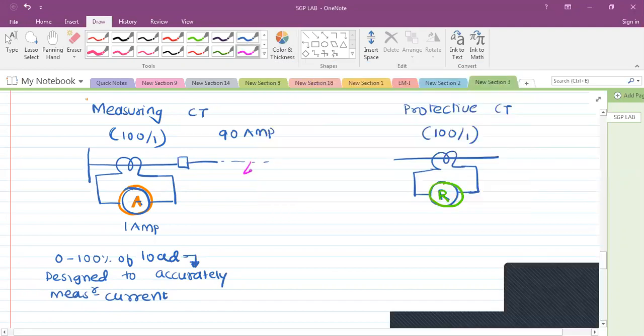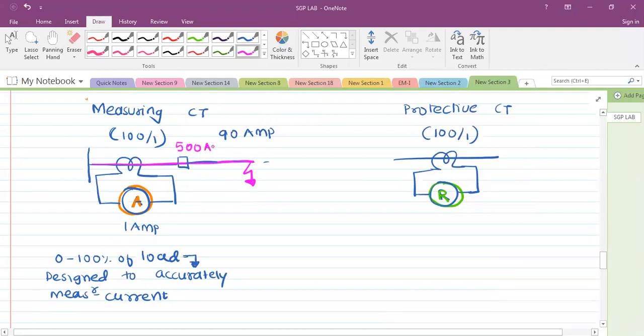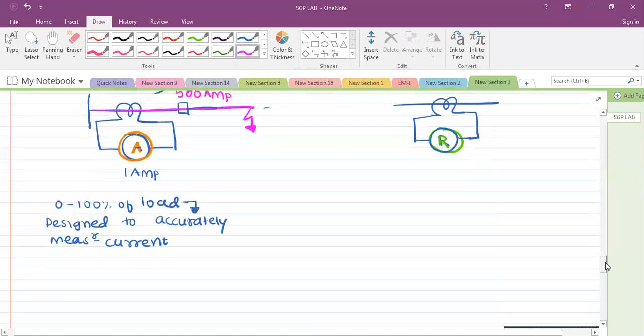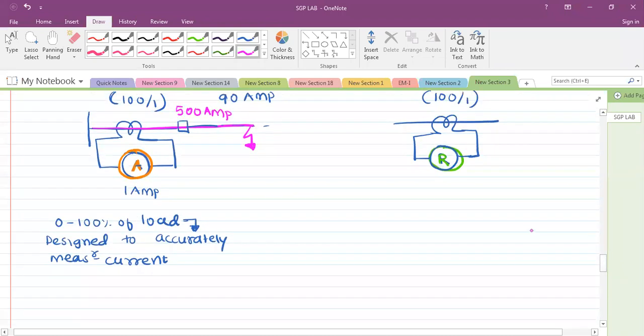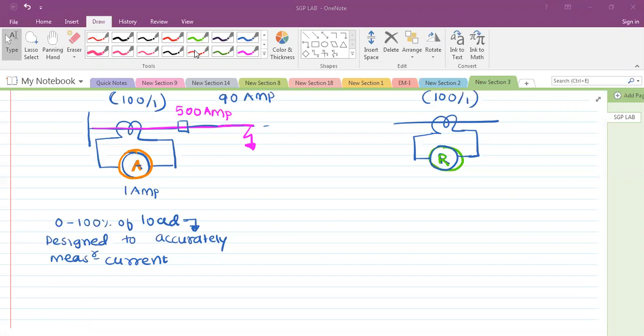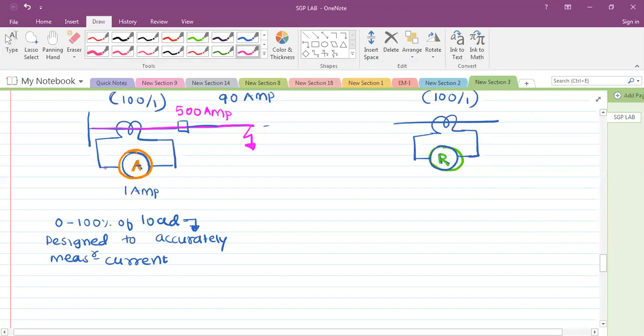But suppose a fault occurs on the line and the fault current is 500 ampere. What will be the current through the relay coil? Sorry, the meter coil. What will be the current through the meter coil? 100/1 CT. Primary current is 500 ampere. What will be the secondary current in the event of the fault? 5 ampere. So that 5 ampere will flow through the meter coil. What will happen to the meter?